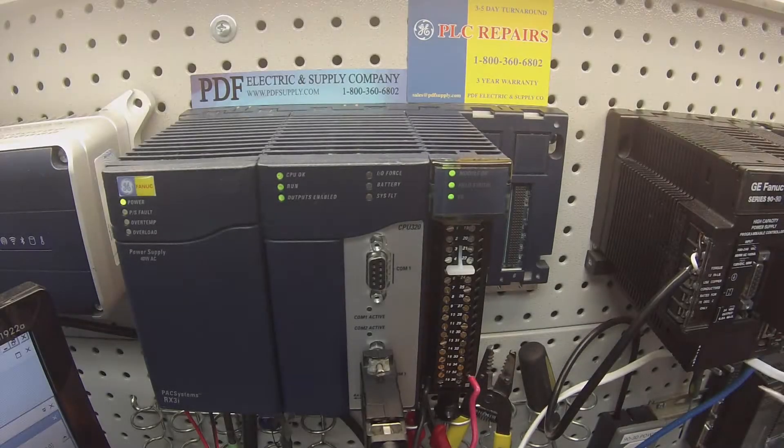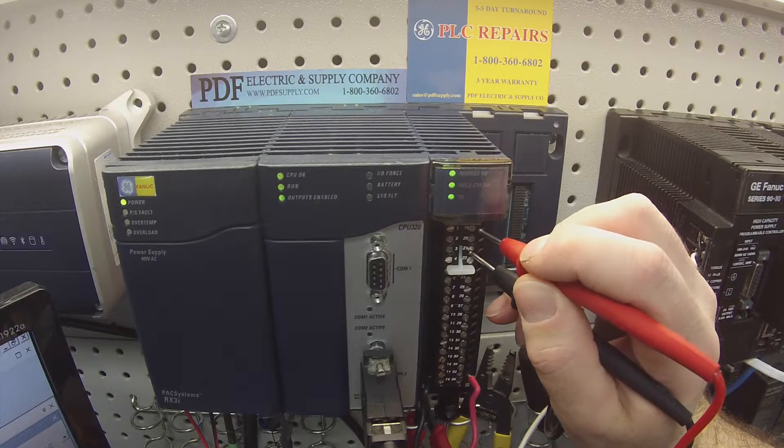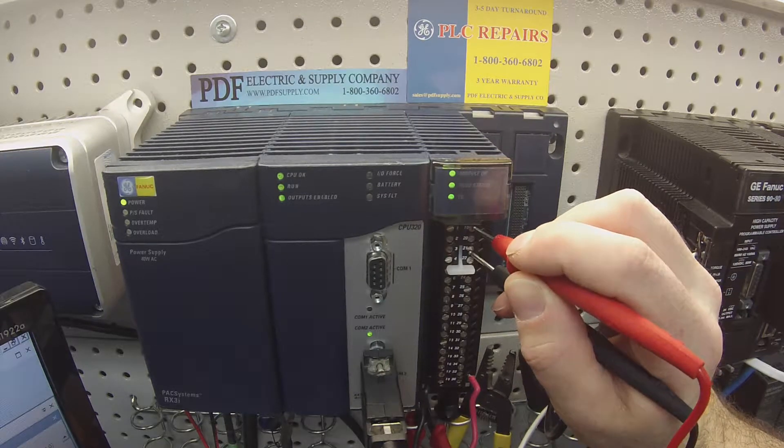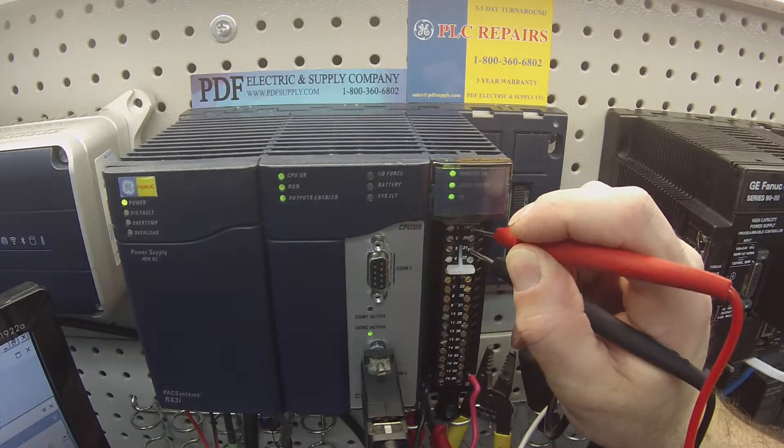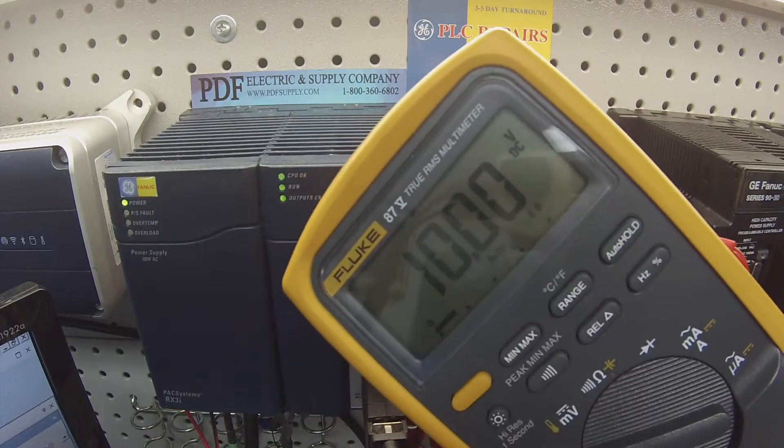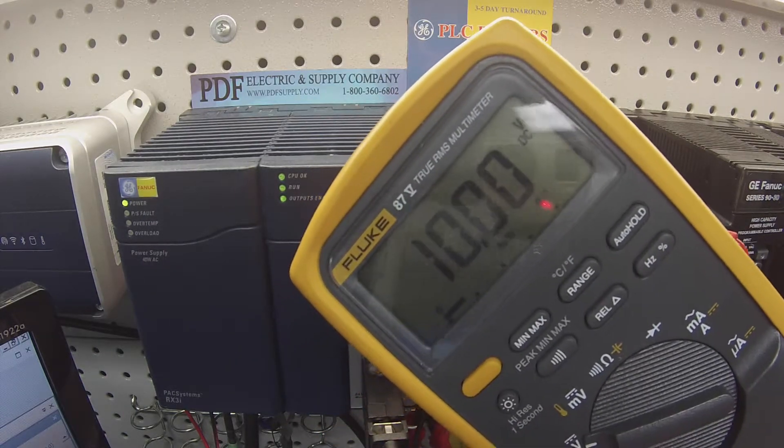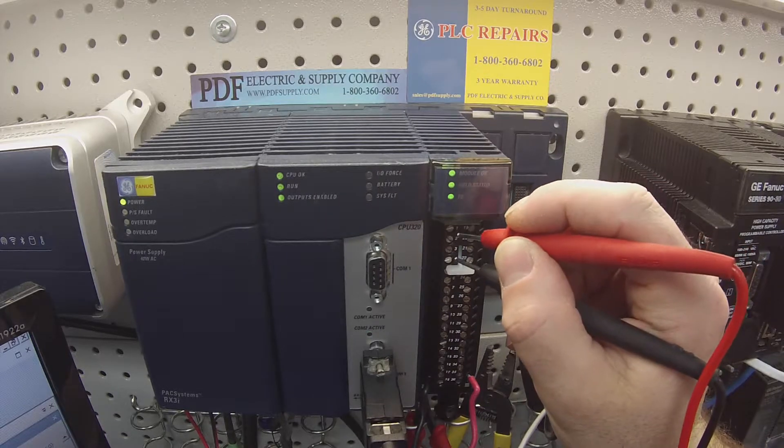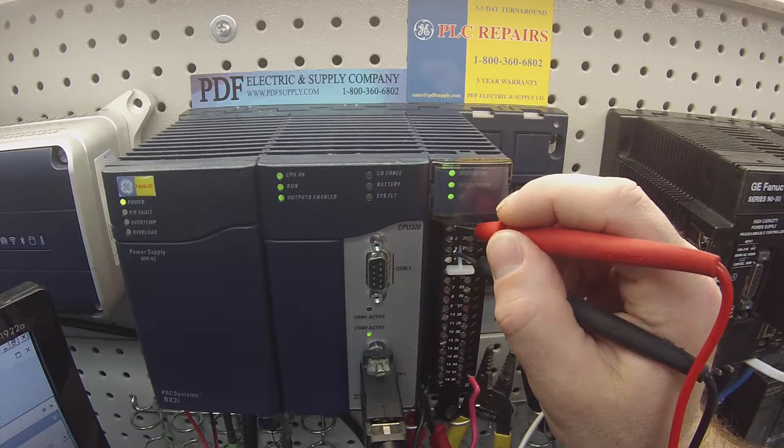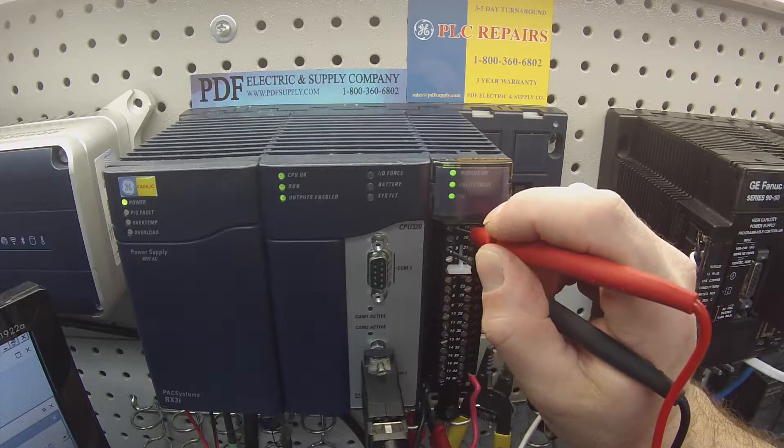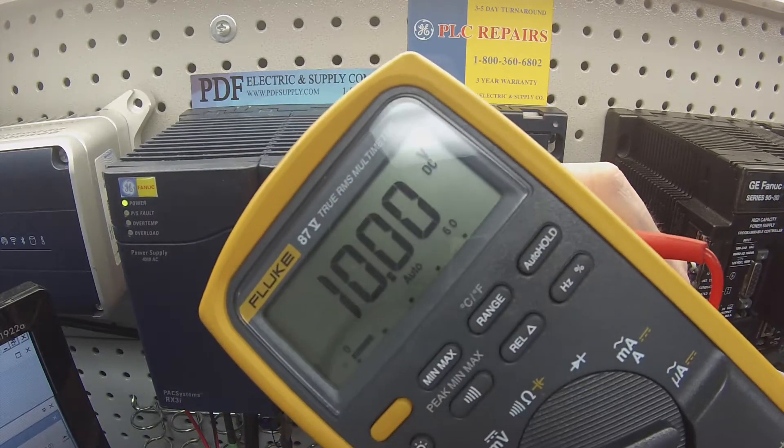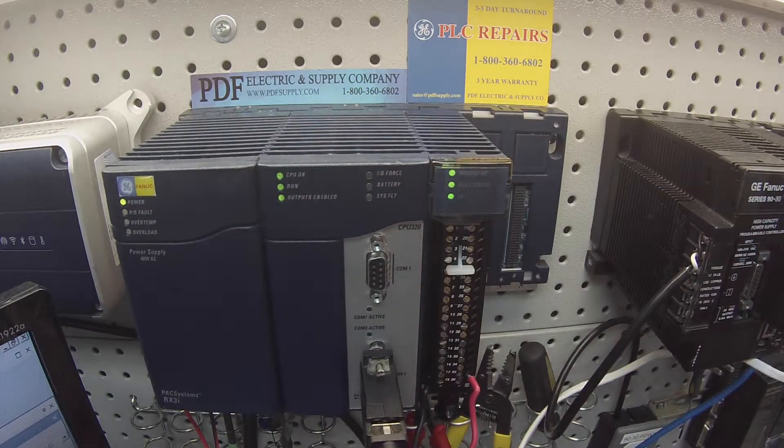So I'm going to place my negative lead, my negative probe on number 21, and my positive probe on number 19, and I'm looking for a value of 10 volts, and I have that perfectly. Then similarly, we're going to jump over to channel number two, positive lead on number one, negative lead on number three, 10 volts, and that's good.